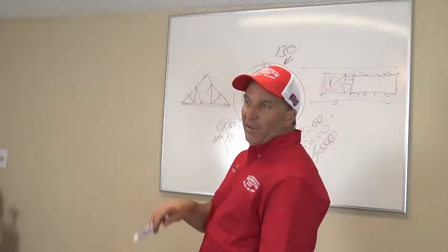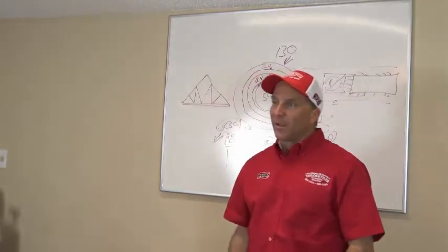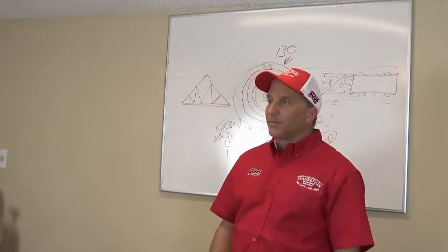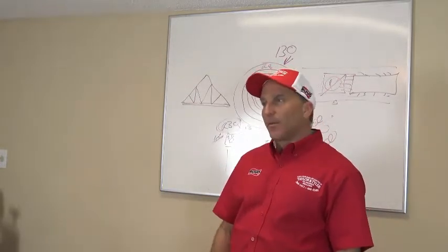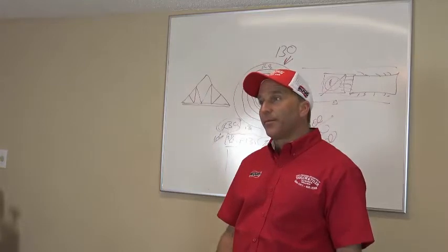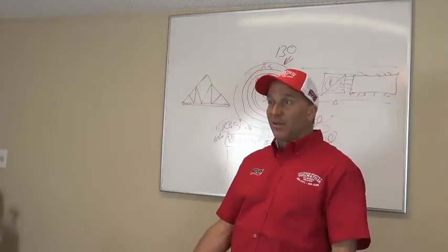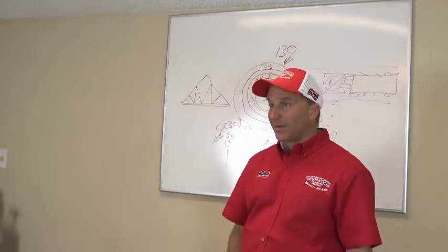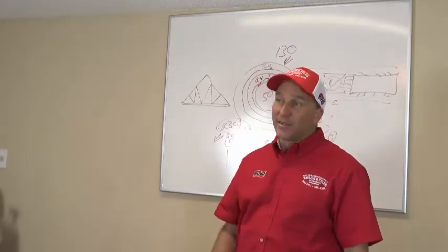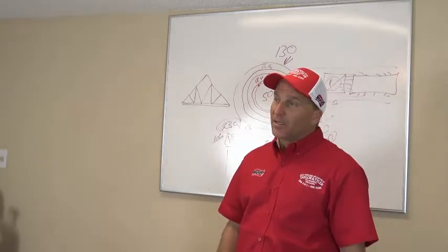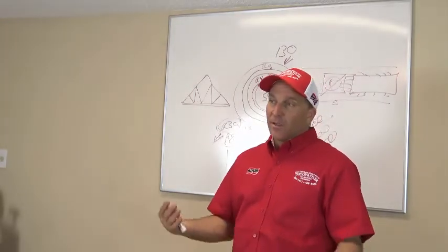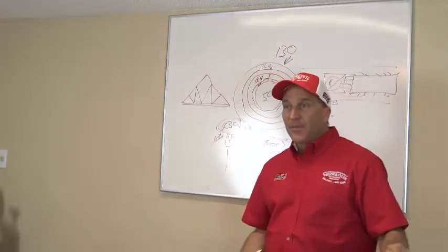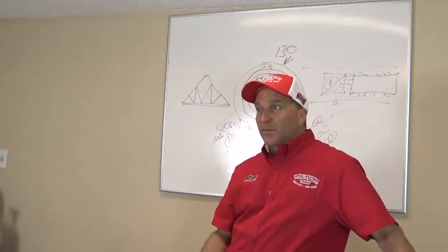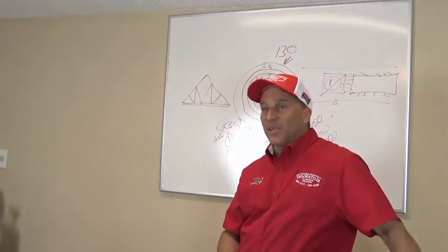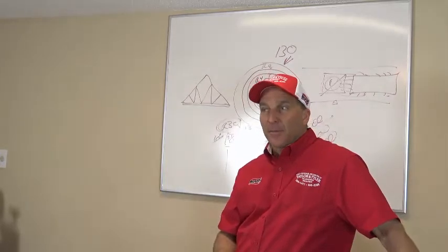So now that you cleaned everything there, then you go, ma'am, after I pulled your blower wheel out, I looked up inside there and your coil's dirty too. So I can come back tomorrow and I can clean your evaporator coil. It's $650 to clean your evaporator coil though. So your blower wheel definitely obviously needed to be cleaned. I showed you how dirty it was and I showed you how clean it was when I put it back together. Now that we got that clean, your next thing is your evaporator coil, and it has to be done too because it's filthy dirty and it's going to restrict airflow through the system. Your superheat, your subcooling is going to be off. But I couldn't see it because of the way your system is installed. But now that I pulled that blower wheel out, I was able to get my body in there and actually see it. So that's what needs to be done next. You ready to get that done?